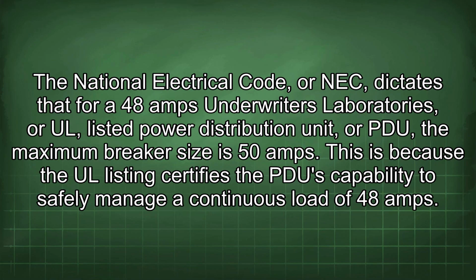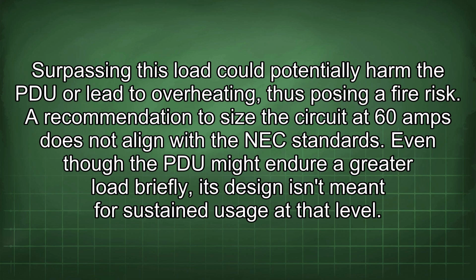The National Electrical Code, or NEC, dictates that for a 48 amp Underwriters Laboratories, or UL, listed power distribution unit, or PDU, the maximum breaker size is 50 amps. This is because the UL listing certifies the PDU's capability to safely manage a continuous load of 48 amps. Surpassing this load could potentially harm the PDU or lead to overheating, thus posing a fire risk.